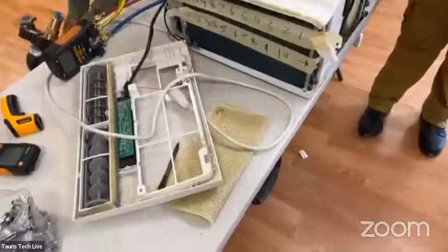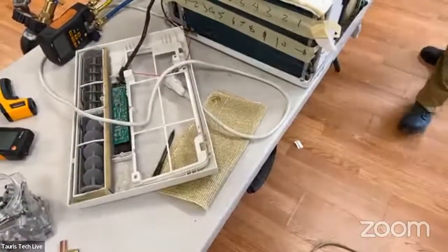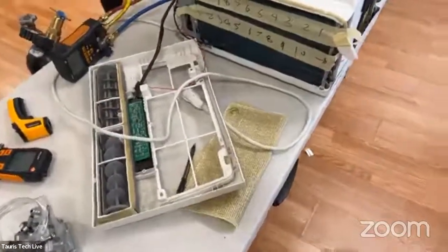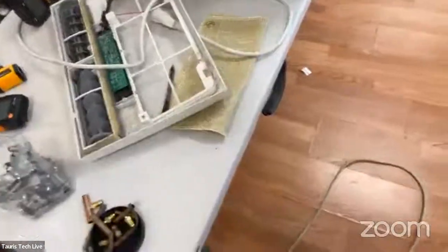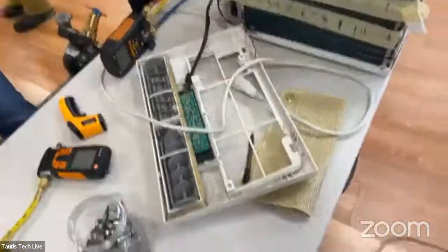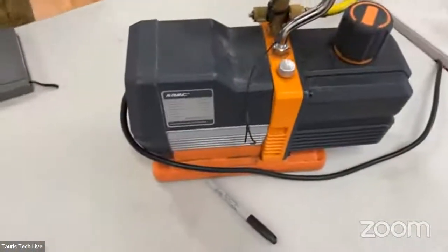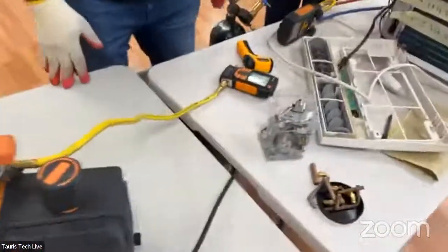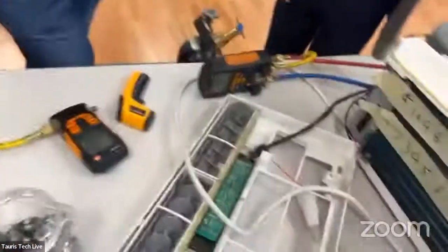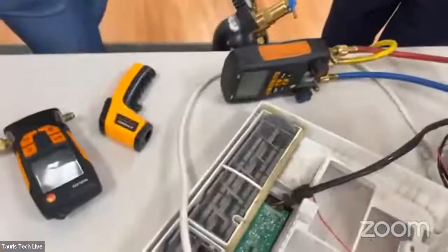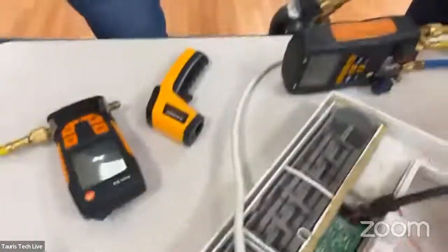So for the second time, do we just connect the vacuum, or do we need to dump the nitrogen out? Oh, you always have to dump the nitrogen. If you put pressure through the vacuum pump, it can mess up the seals on the vacuum pump. We have to evacuate the lines also. So you close your valves.